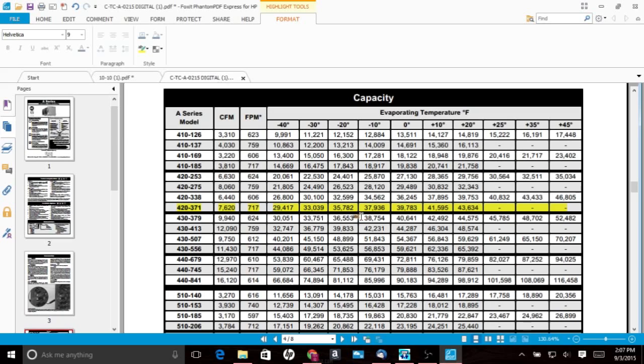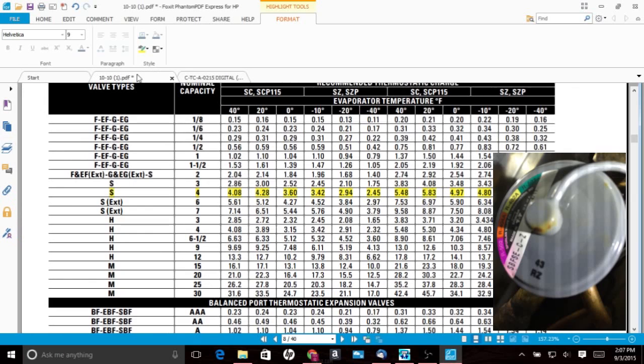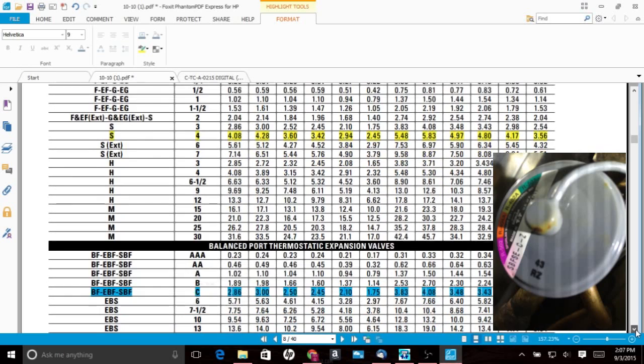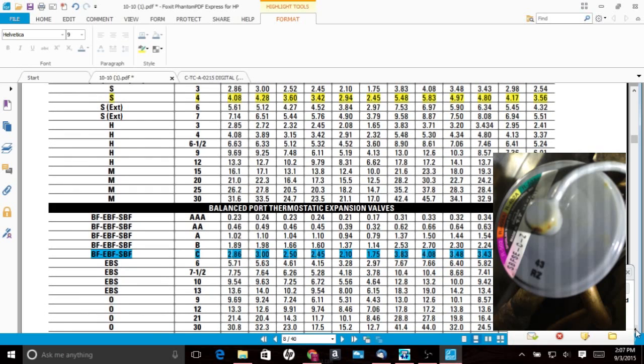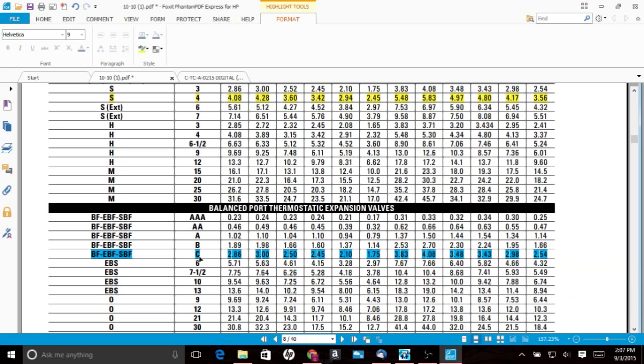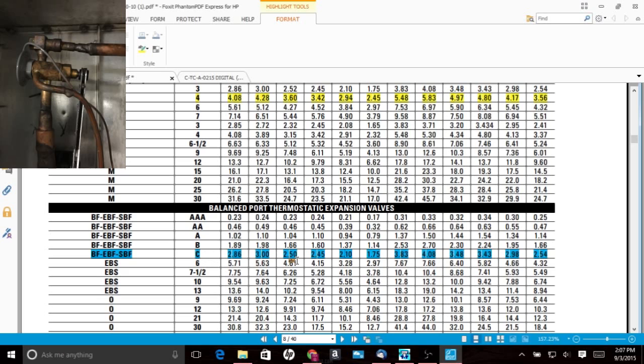And then if we come over here and take a look at our Sporlan valve sizing, I'll show you the picture if I can get it in the video. The valve that's currently on this unit is this valve right here, an SBF-C. It's a little bit different. It's a balanced port expansion valve.